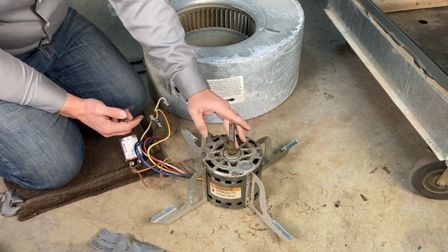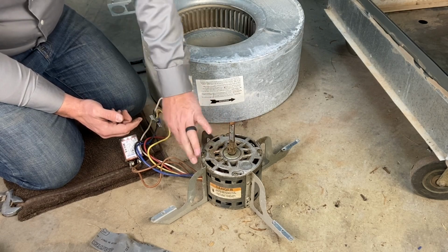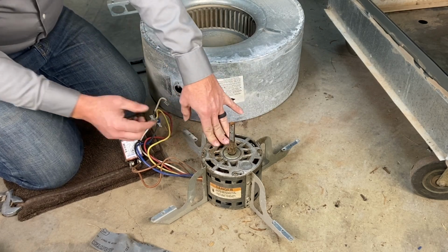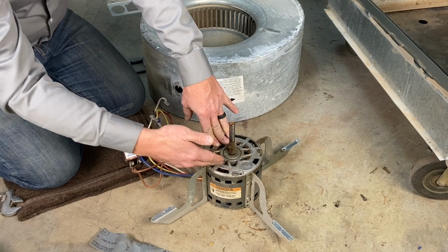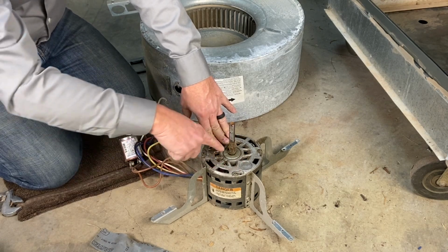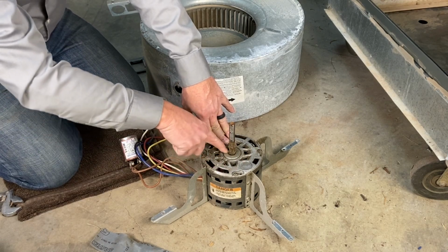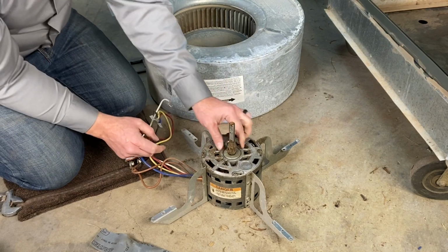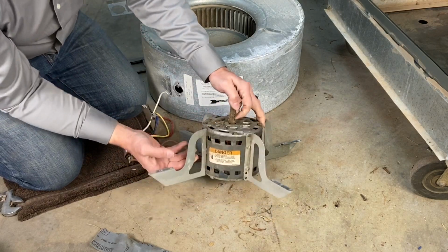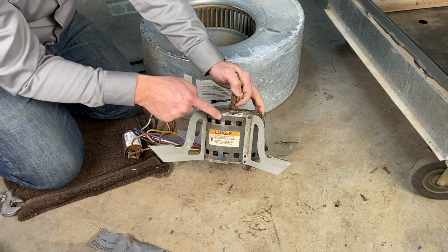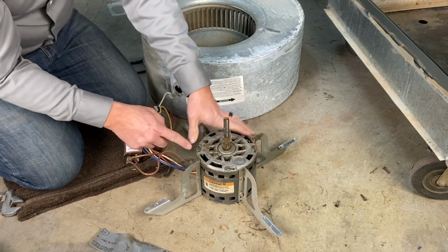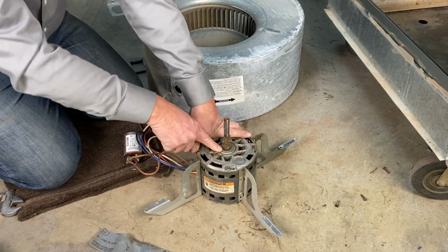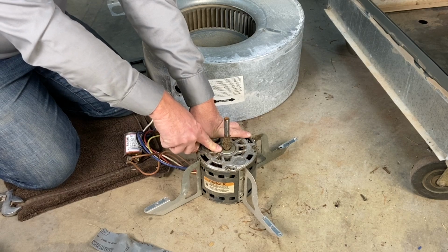So we also want to clean this motor up. We'd use rags, we'd clean all this up. We'd take a CO2 tank or some kind of tank and blow a lot of the windings out. We also want to make sure we don't put too much air pressure here, because we don't want to blow any of that oil out of that grease packing. On this motor, we also see there's a little bit of a grease ring right here. That's a good indication that this sealed bearing may be losing some of its grease already.